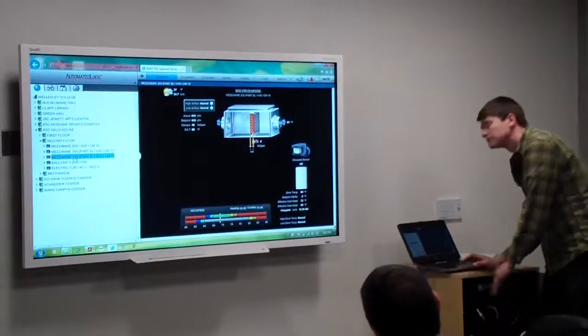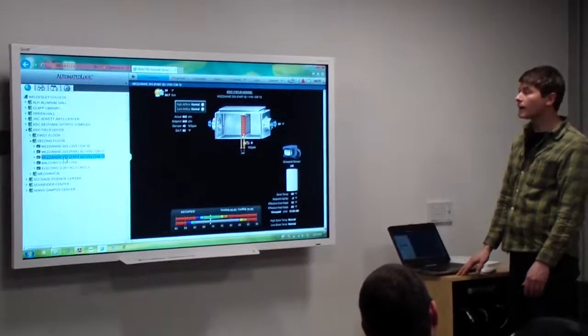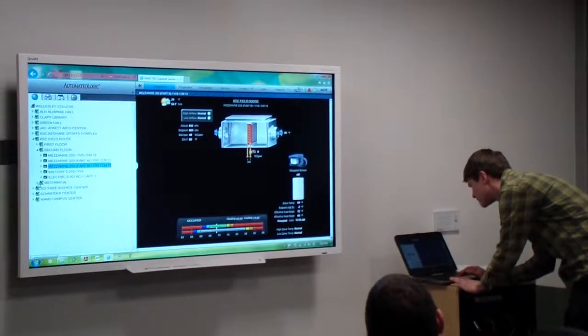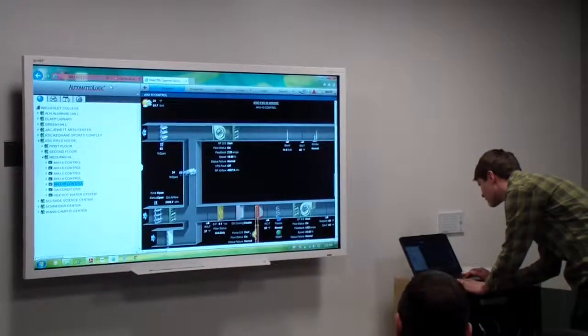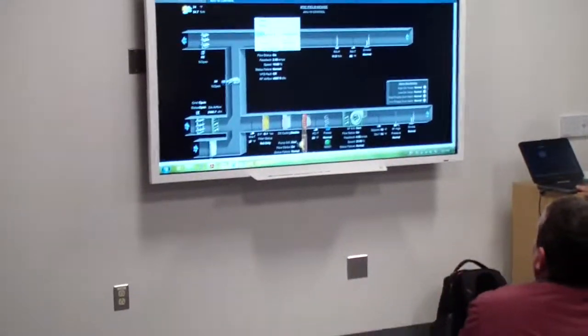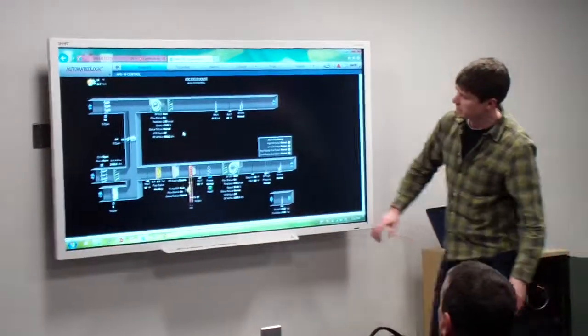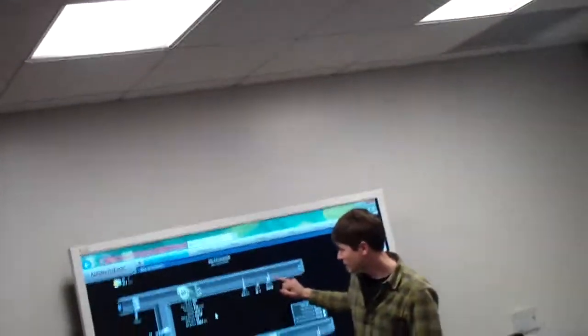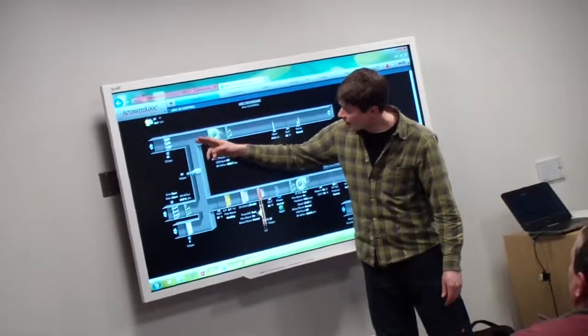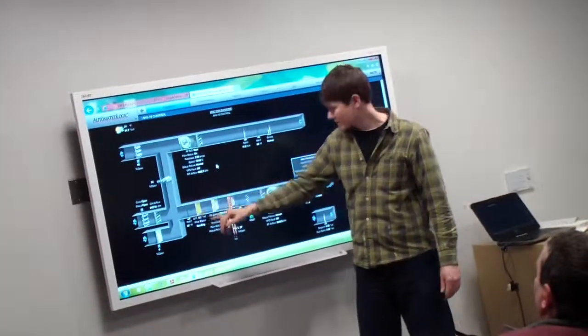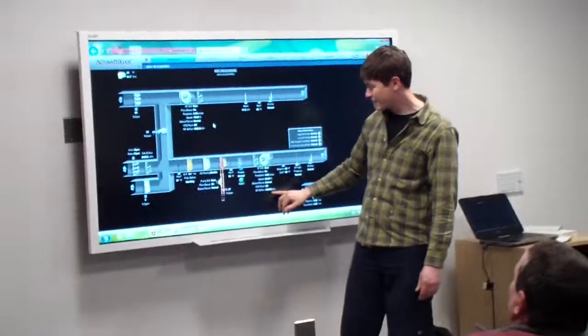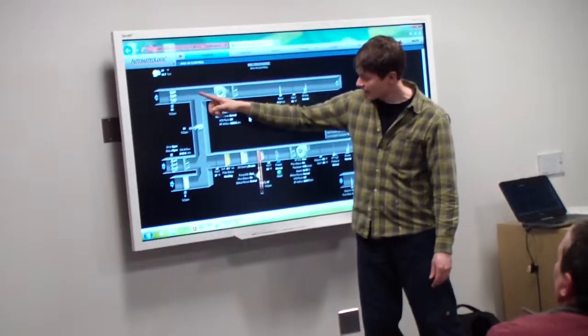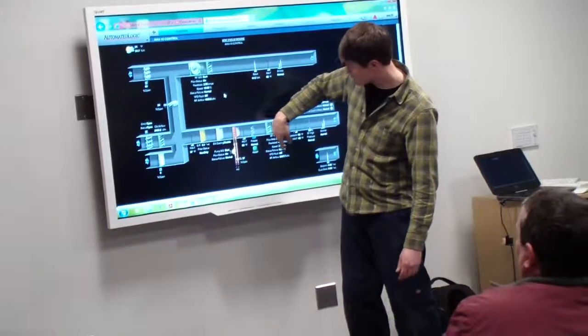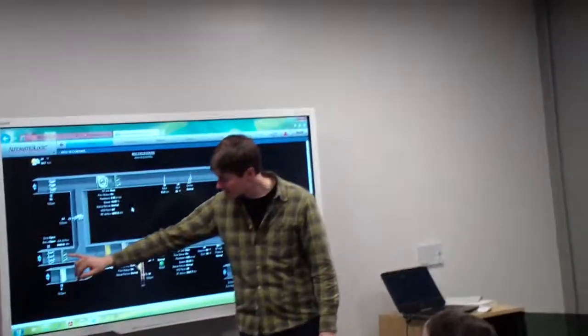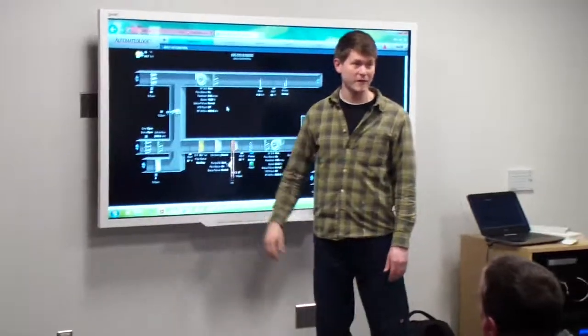Can you tell how much outside air or fresh air is being introduced, to Martha's question? At the moment, yes. If we move up to AHU10, what you can see here is that you're bringing in 2,400 CFM of outside air into the unit, and you're returning 4,900, some of which is getting expelled, some of which is being returned. So now you're looking at 3,800 coming into the unit. You're expelling 1,000 CFM out, whatever the difference is. So you're bringing in 2,400, 2,500 CFM of outside air into the building.